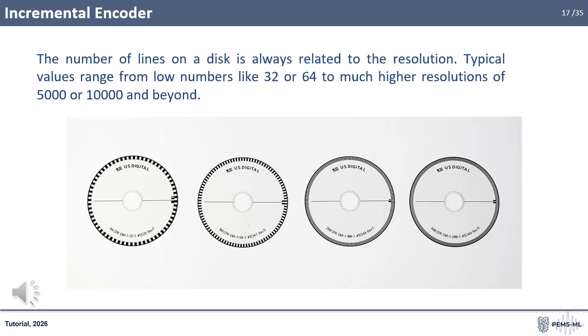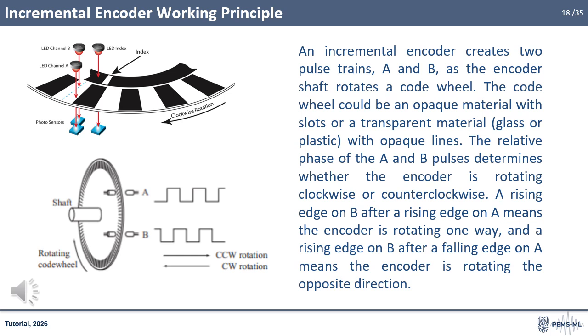The number of lines on a disk is always related to the resolution. Typical values range from low numbers like 32 or 64 to much higher resolutions of 5,000 or 10,000 and beyond. The following picture shows several encoder disks. Lower resolutions are on the left and higher resolutions are on the right. An incremental encoder creates 2 pulse trains, A and B, as the encoder shaft rotates a code wheel. The code wheel could be an opaque material with slots, or a transparent material, glass or plastic, with opaque lines. The relative phase of the A and B pulses determines whether the encoder is rotating clockwise or counterclockwise.